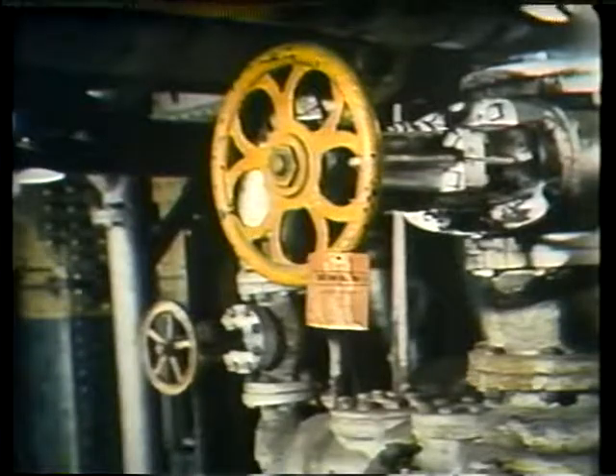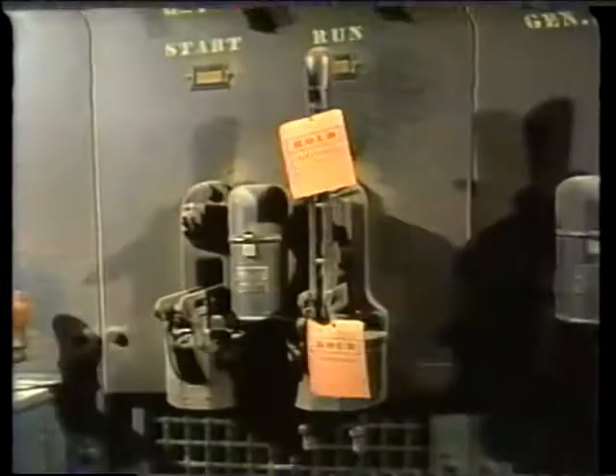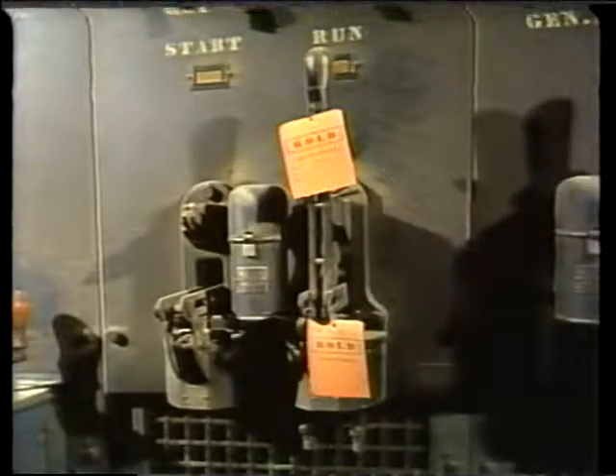So, how do you tag out a piece of equipment? Well, first step is to find out just which components need to be tagged to ensure that you are completely isolating the equipment that you're going to be working on. Now, you'll need to tag out mechanical components such as valves and electrical components such as switches or breakers.